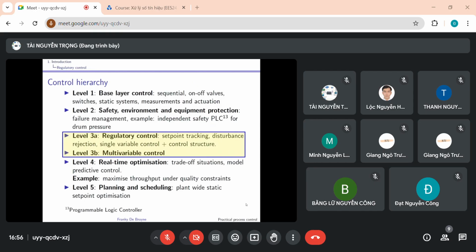Process control can be represented as a hierarchy. Level 1 corresponds to base layer control. This level is also sometimes called the field level. These are the devices, sensors, actuators, proximity switches, on-off valves, and so on that you can see in the field. The control that is associated is typically sequential in nature. Level 2 is the safety level. It involves environment and equipment protection. Safety instrumented control systems, so for example safety PLCs, that are physically separated from the general purpose control system, monitor the system and intervene when dangerous situations arise.